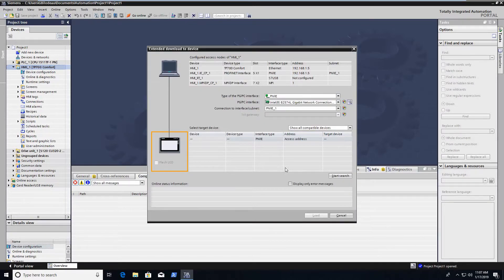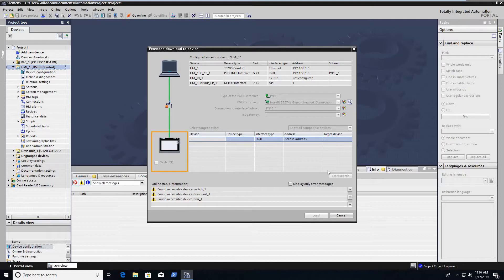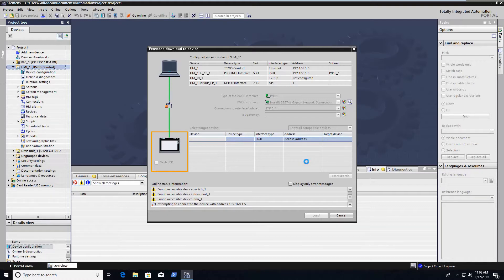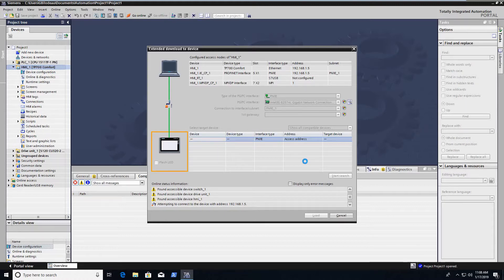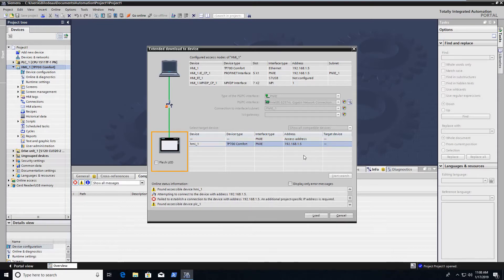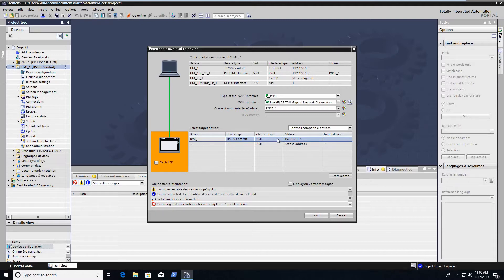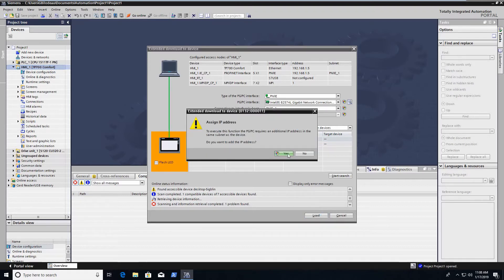Now I'm going to do a download. The first time you do the download you've got to go out and find the device that you want to download to. This also makes sure that you pick the right type of device, the right part number, the right communication protocols. So it does some additional checks, not just the scan as the network scan does. So there it's found a device that's compatible to everything in your project, so it'll let you pick it and then do a load.